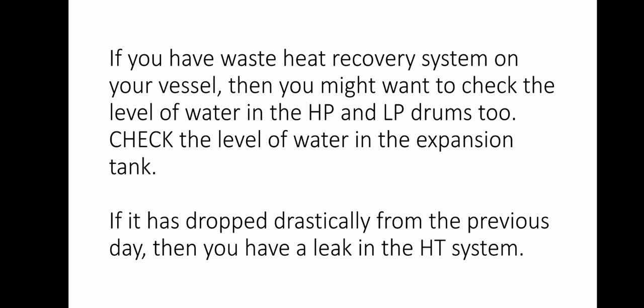When you find the water levels within the limit, there is no problem. You can also check the water level in the expansion tank whether it is good, then move on to the next area. If the level in the expansion tank has dropped drastically, you have to fill it to maintain the correct level, and if it has dropped significantly from the previous day, you have to check the system thoroughly.